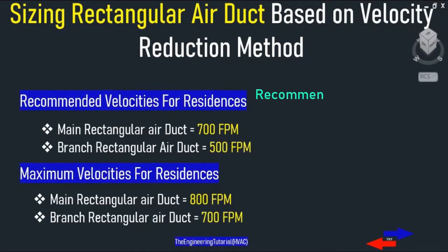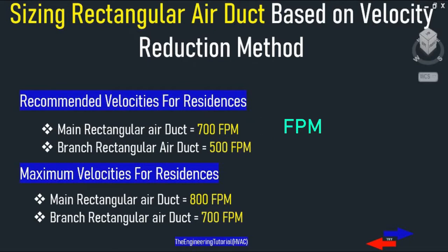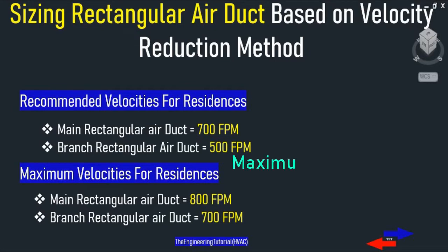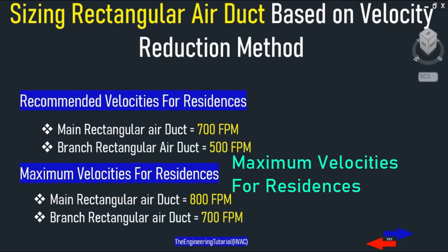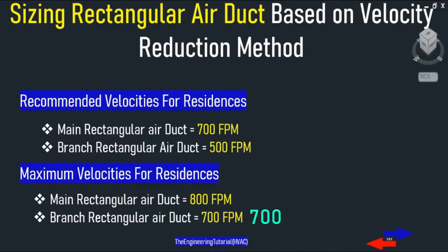The recommended velocity for residential main rectangular air duct is 700 FPM. The maximum velocity for residential main rectangular air duct is 800 FPM, and 700 FPM for branch duct.